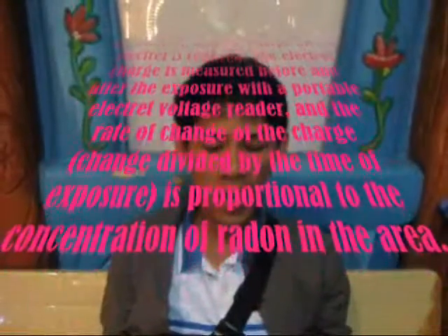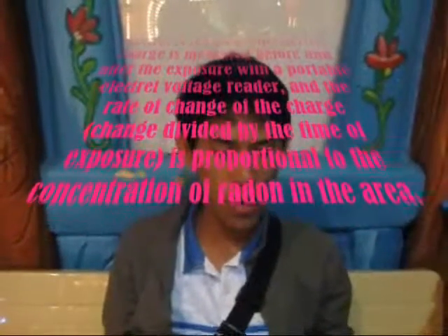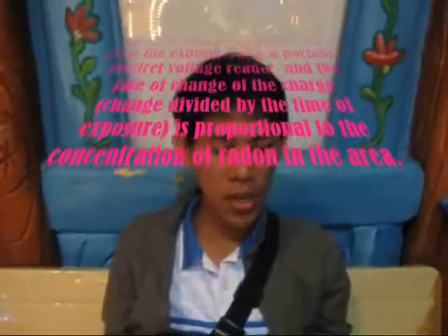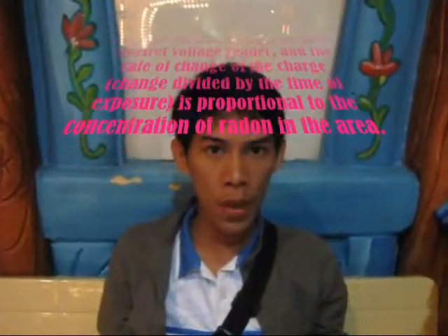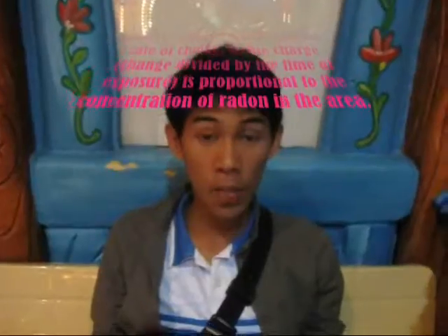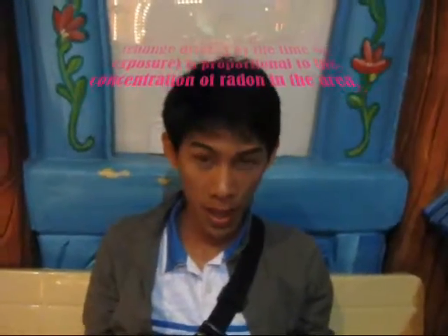The ions are then attracted to the charged surface of the electret, and the charge on the electret is reduced. The electret charge is measured before and after exposure with a portable electret voltage meter, and the rate of change of the charge is proportional to the concentration of radon in the area.